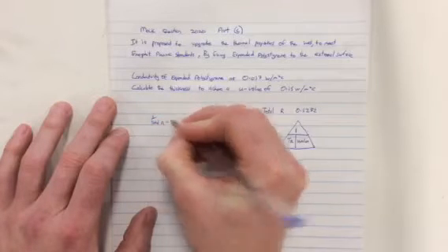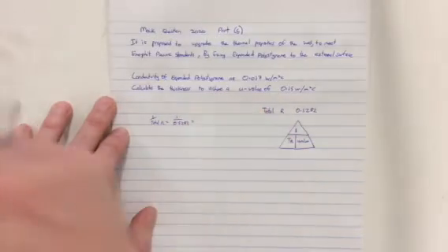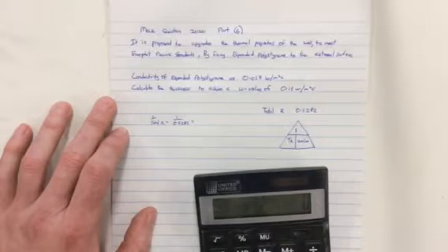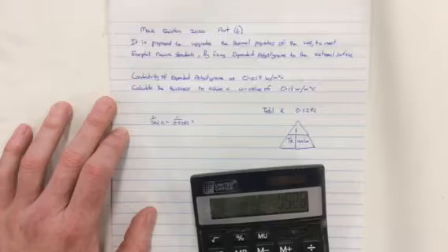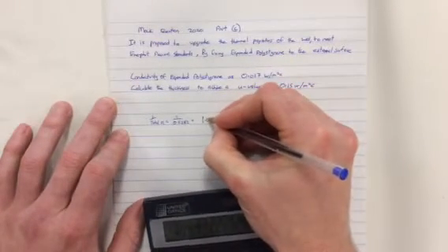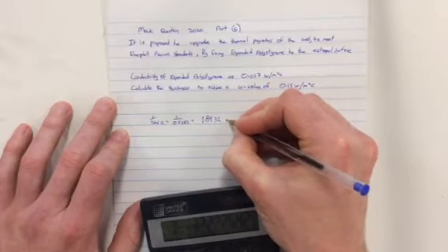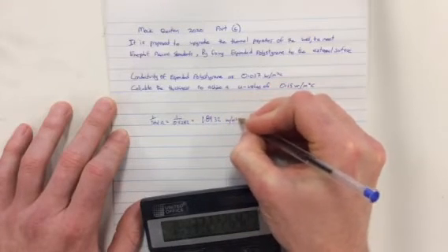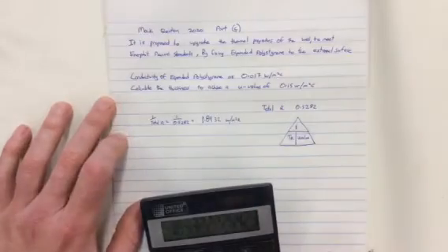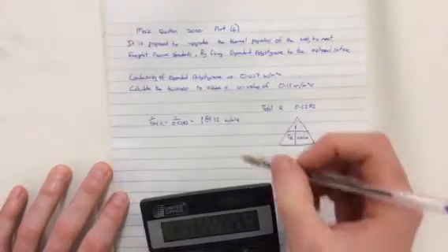1 over total R equals our U value, so then 1 over 0.5282 gives us our U value of 1.8932 watts per meter squared K. So that's the first step. You'd find the U value, and most of you are able to do that.